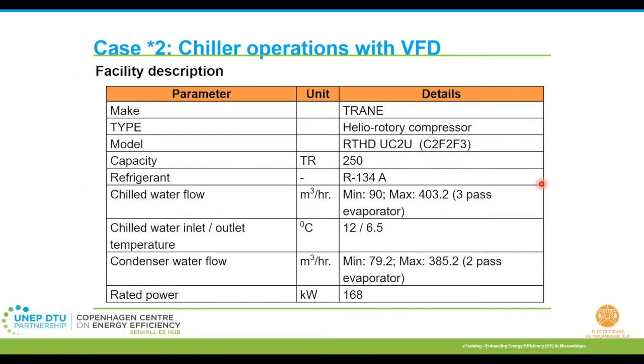Case two is about having a variable frequency drive for chiller operations. Though the technology is available, not many still use it for chillers. Yes, variable frequency drives are used for many other applications, but for chillers specifically, you very rarely come across them, because people are either not aware of it, or yeah. So this has to be looked into. This gives you one of the facilities.